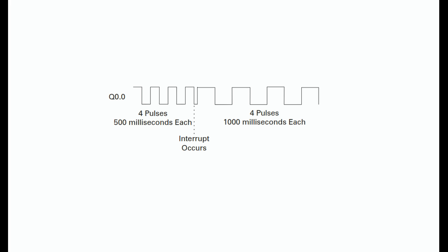PTOs have a 50 percent duty cycle. This means the pulse is off for the same amount of time it is on. The number of pulses and the cycle time can be changed with an interrupt.